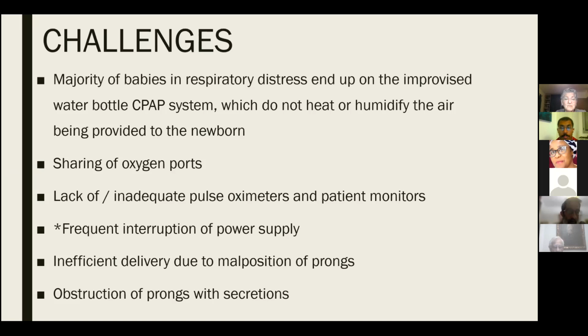Then we also have issues with frequent interruption of power supply. Eventually the generator will kick in all right, but there are times when within a couple of minutes, the lights can go on and off about 3 to 5 times. And then eventually you put the machine back on and it's making a funny noise. Then inefficient delivery due to malposition of the prongs.